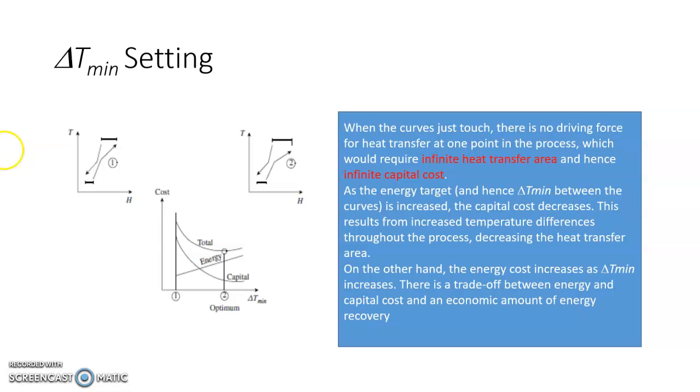So to decide delta T minimum, you have to find out the value of energy and capital costing for various delta T minimums. And for every delta T minimum, you find out the total costing and once you find the total costing, you can easily identify which delta T minimum works well. So this is known as super targeting. We'll see this as we proceed further.